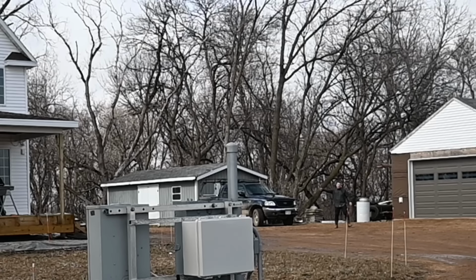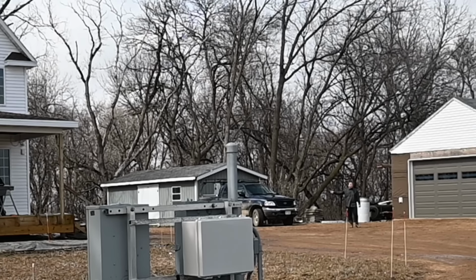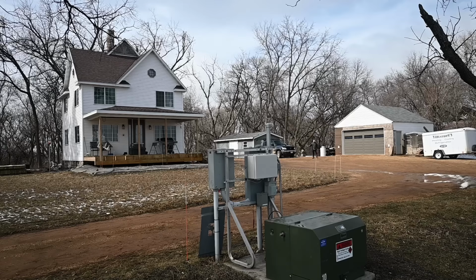Now, coming from the house across this open area back into the grove about 150 feet, we have a copper gas line that is acting as a grounding electrode right now because there is no dielectric union installed where that pipe goes into the ground. We're going to be solving that in a future video, so make sure you subscribe if you want to see that. But in any case, that's a very significant grounding electrode right now, and so we have a percentage of that 0.4 amps that is flowing into the ground through that grounding electrode.